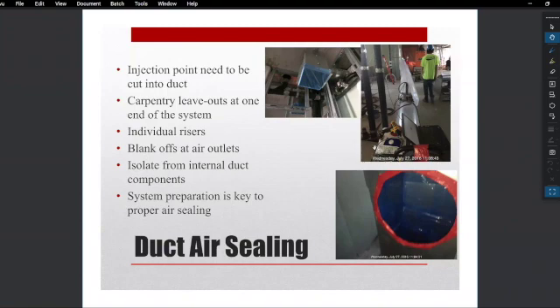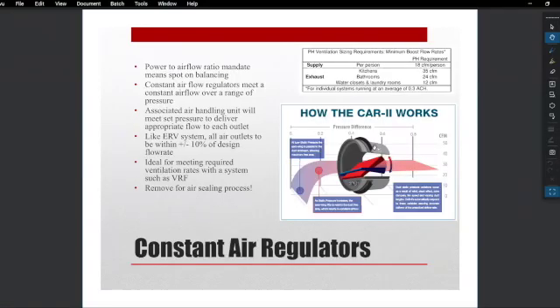Basically, all it is is you're sealing the interior ductwork with an aerosolized emulsion of water and a vinyl acetate polymer, and the polymers stick to irregularities in the ductwork, like holes, and fill them in slowly. As they're doing this process, they're taking real-time measurements of the leakage or the pressurization in the ductwork, and they can tell when they've hit the threshold and when to stop the air sealing, because the threshold is basically your leakage rate. The preparation is really crucial for the air sealing process.